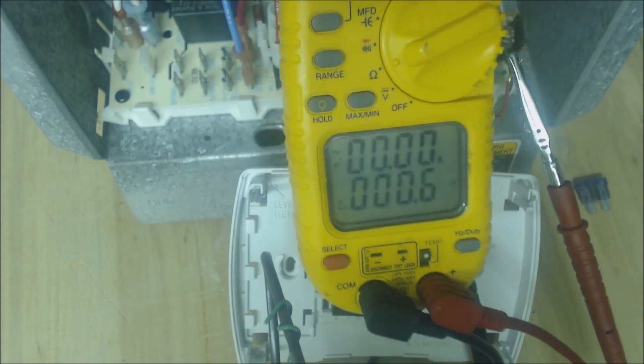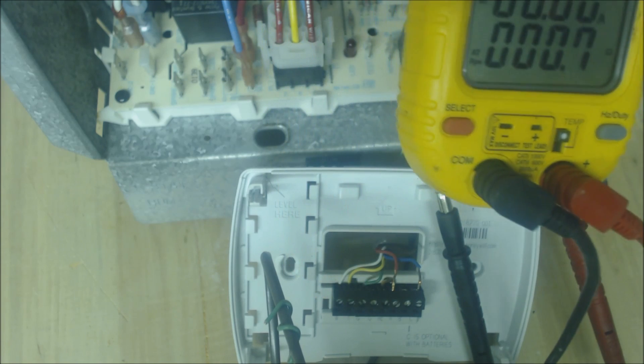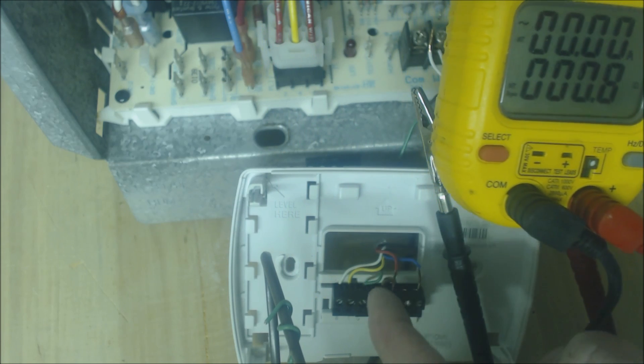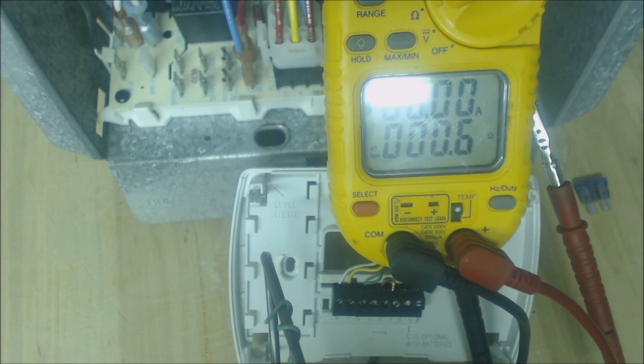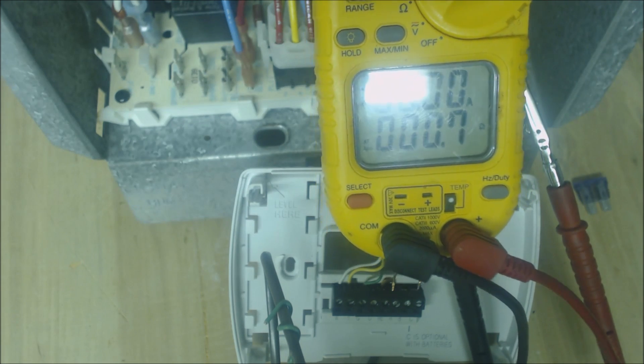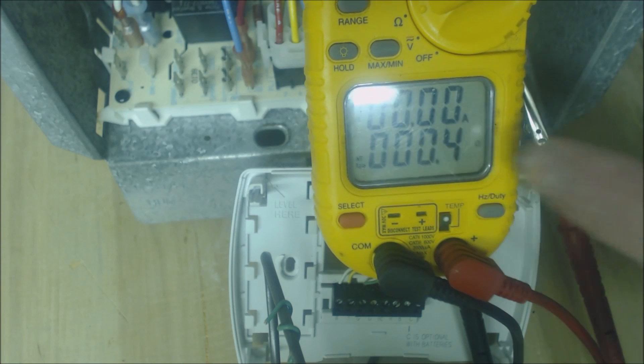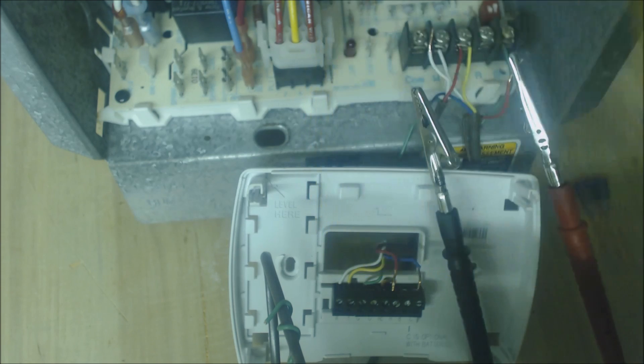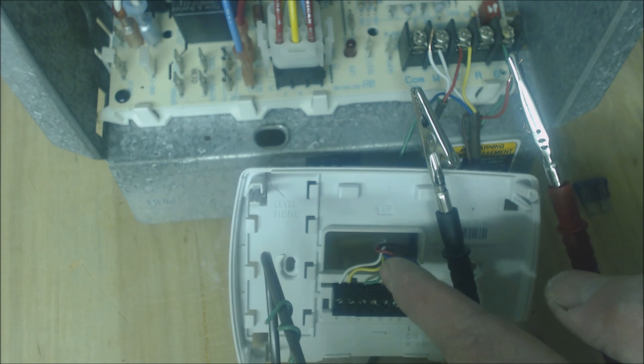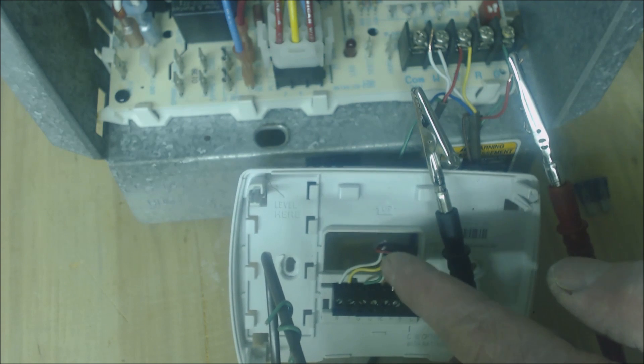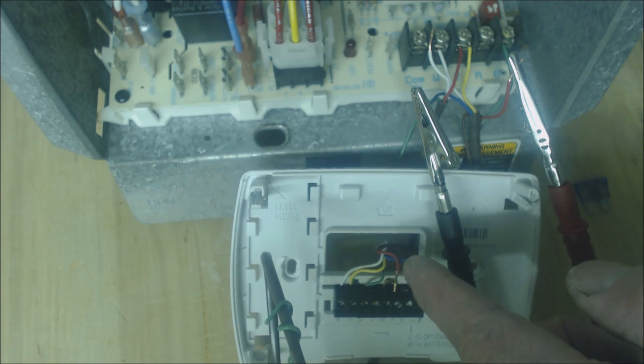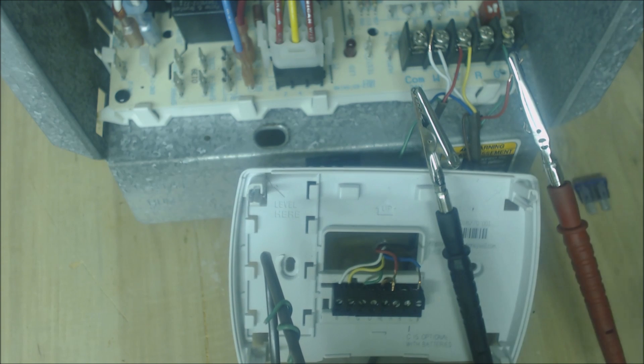We still have the same problem. We've disconnected the red and the blue wires, but somehow the problem must be near because as we move the wires around, the resistance value is getting less. The resistance value right around here must be changing just due to us moving the thermostat wires.